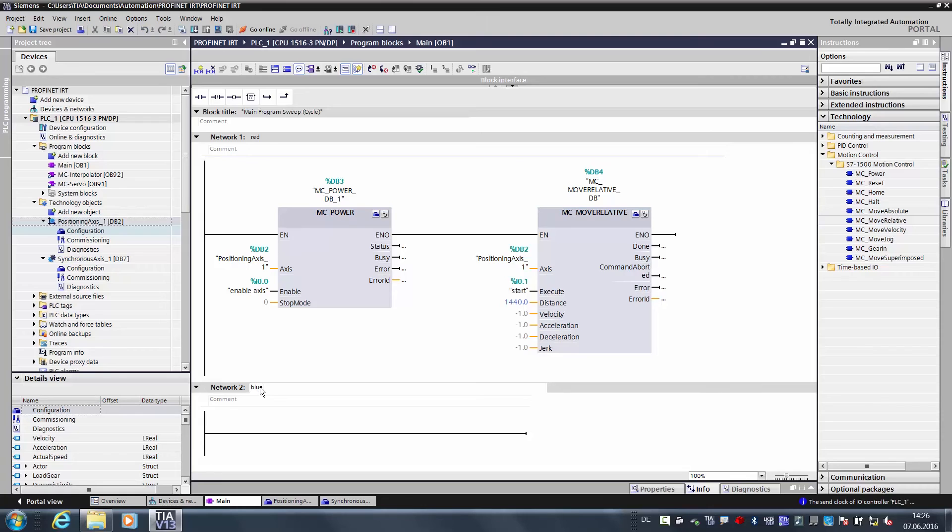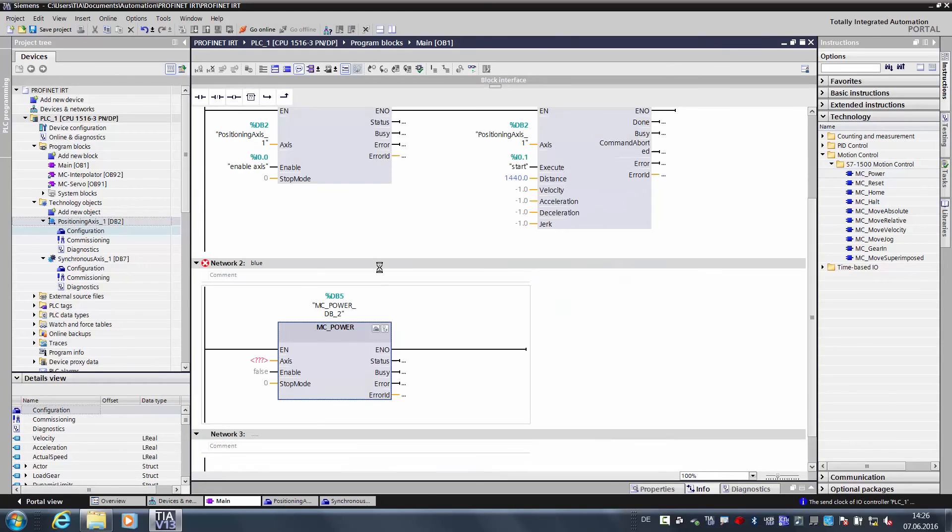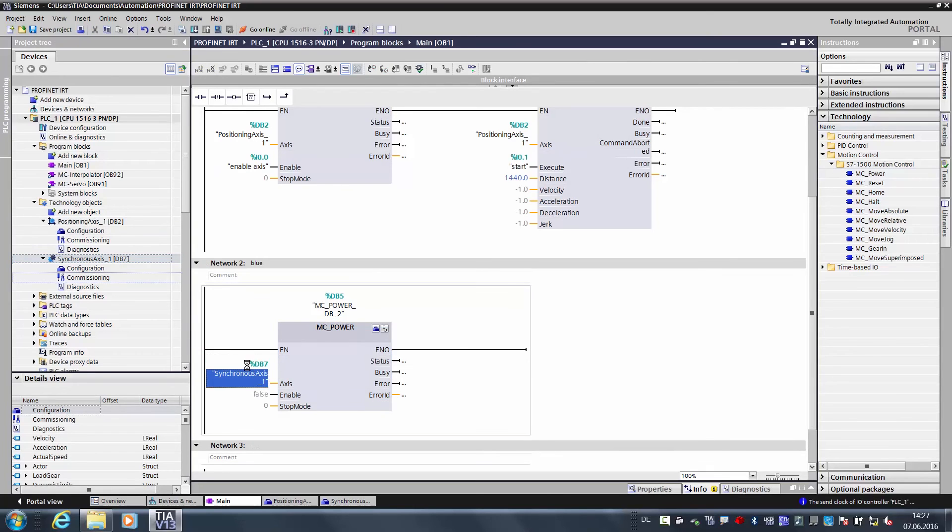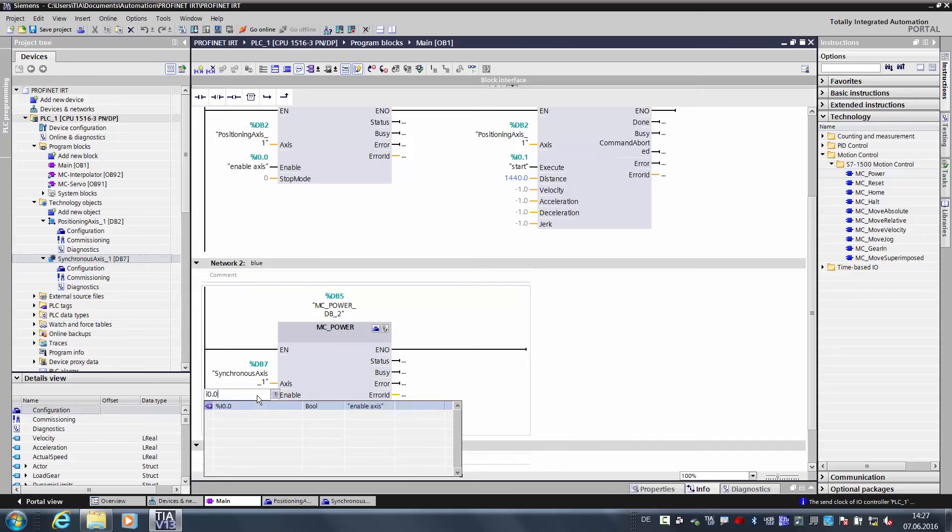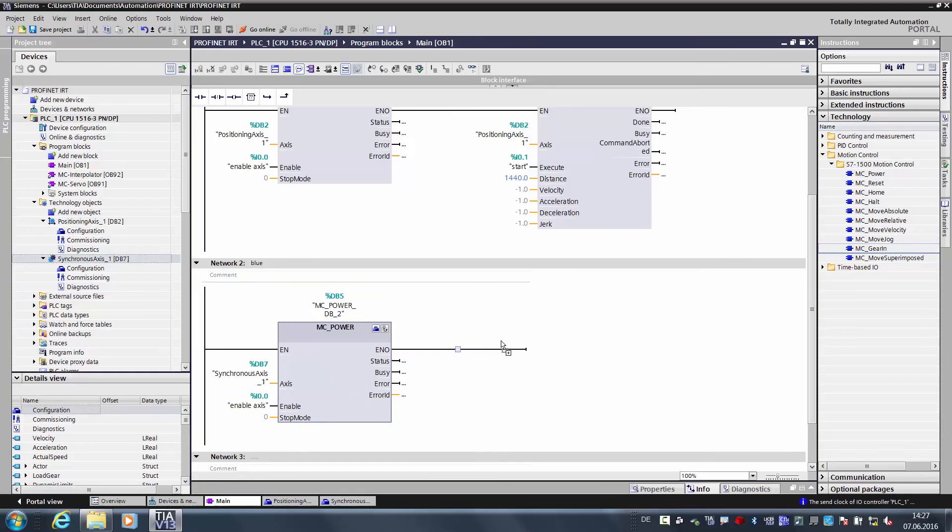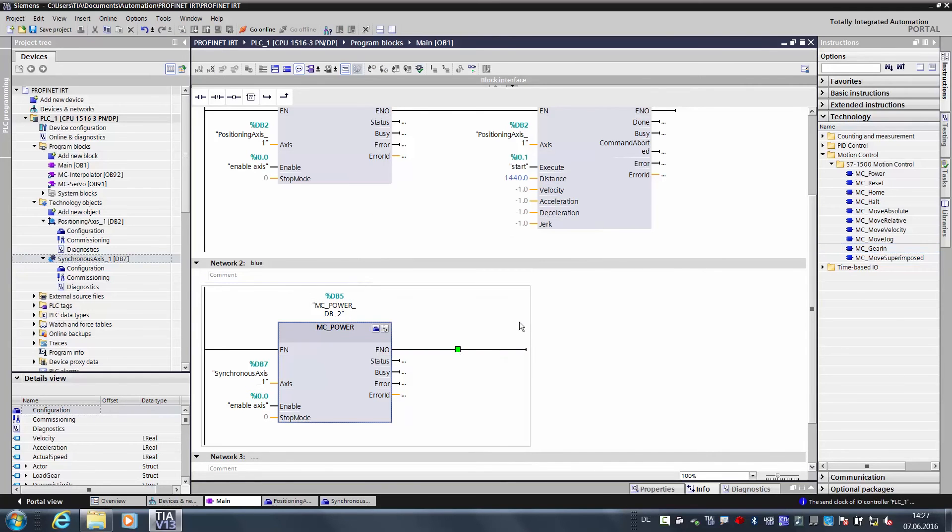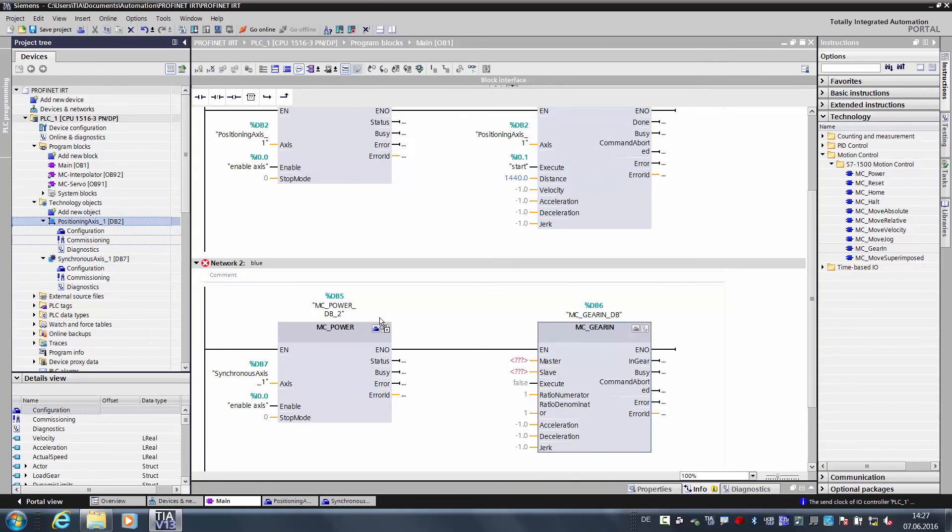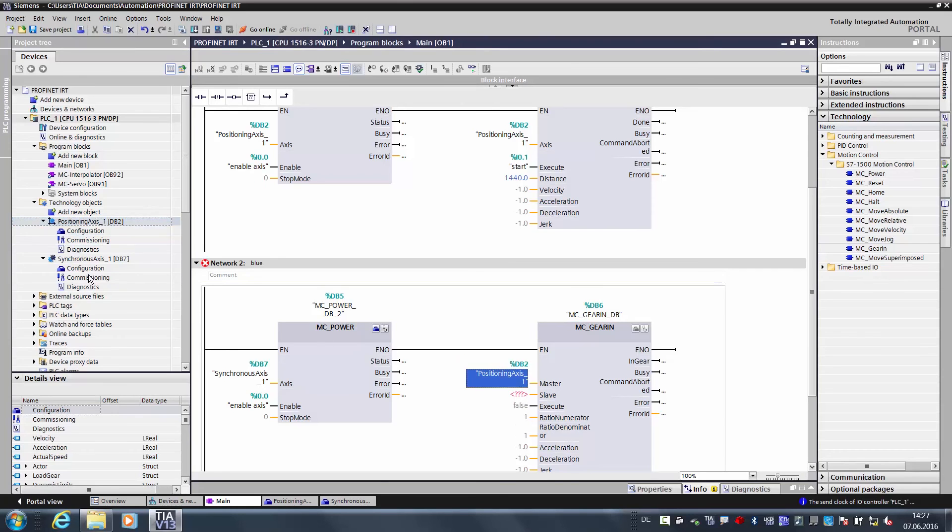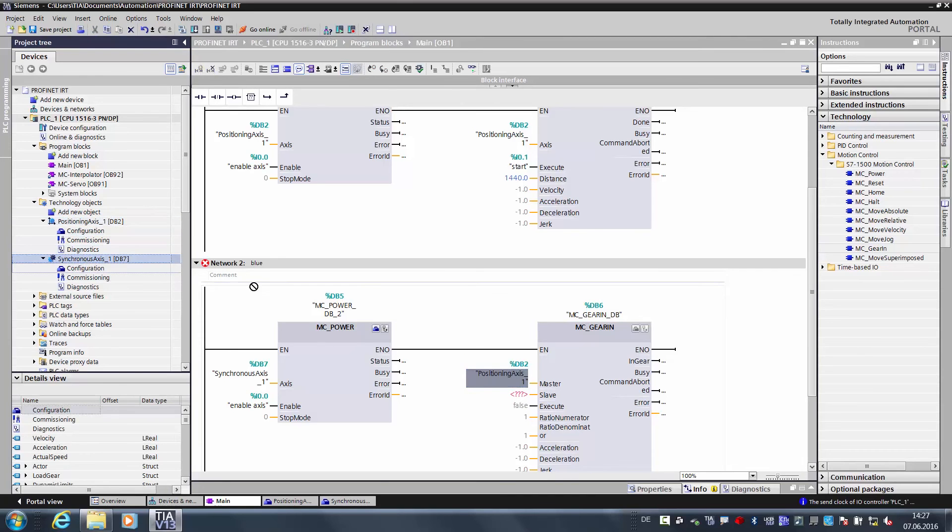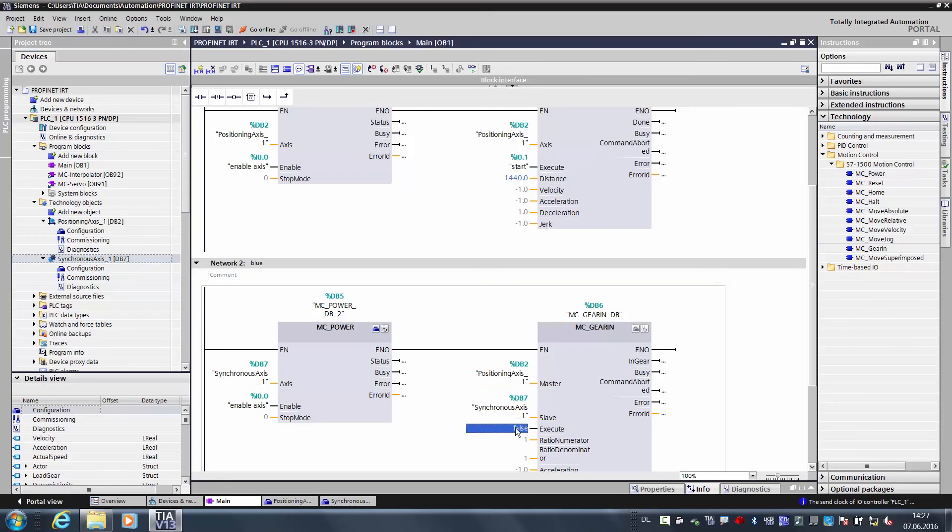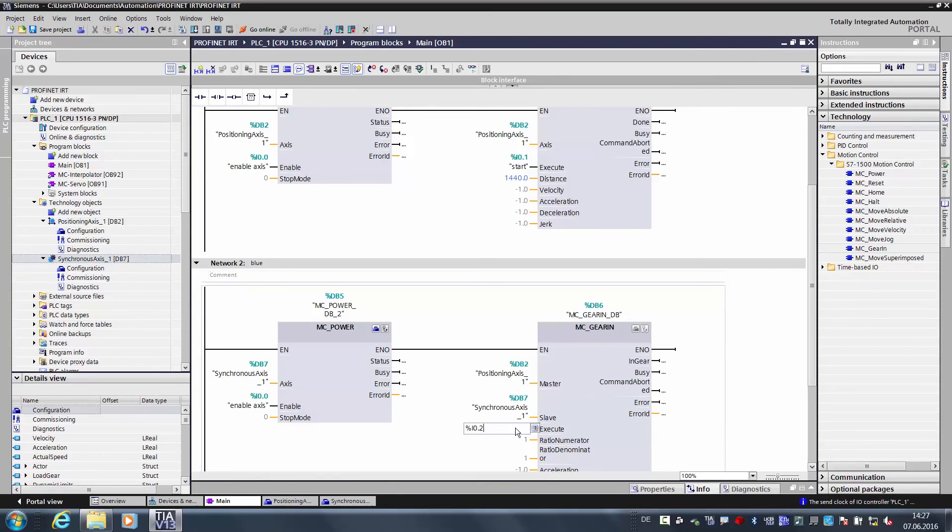Next, we create the blue axis. There we also need an MC power in order to switch on the axis. Here we want to switch on the synchronous axis, so we use the same input as above, the input 0.0. And then we enter the MC, and with this step we couple the slave axis to the master axis. The master axis is our positioning axis. The slave axis is the synchronous axis, and we couple it with the input 0.2.